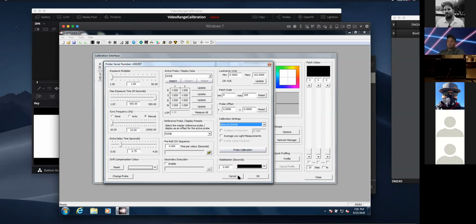Colorimeters are not display agnostic, right? So if you're measuring with a colorimeter, your results are in essence only as good as the matrix you're using and the spectra that was used to create those matrices. And do remember that monitors drift, but probes also drift. So if it's been 5 years since you've had your colorimeter calibrated, definitely send it in for new matrices. Those ideally should be redone every year.